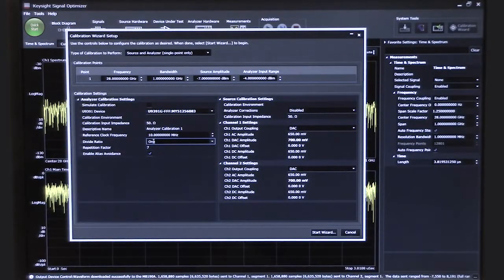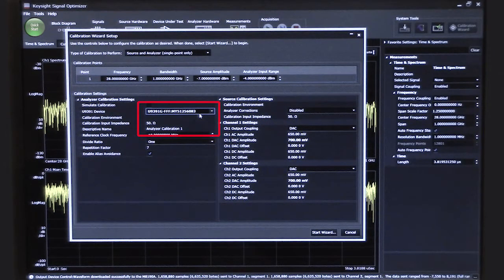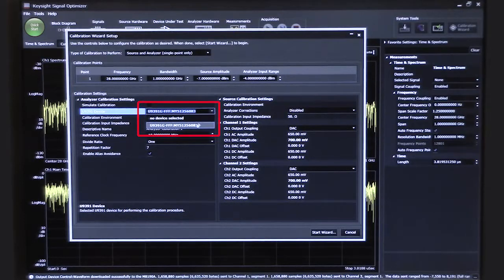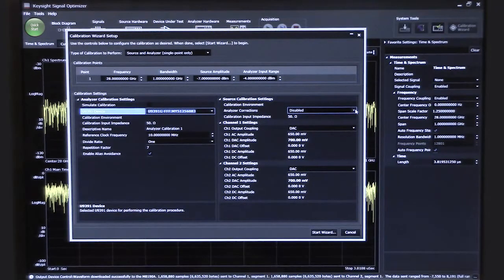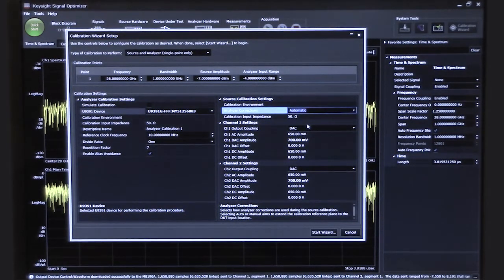On the bottom part of the display, we have more detailed settings for both the analyzer calibration on the left and the source calibration on the right. The most important part on the analyzer side is selecting the comb generator that will be used — this is going to create the test signals we will use to calibrate the analyzer. We can see the model number and serial number of the comb generator. On the right side, we have the source calibration settings, and we want to enable the corrected results on the analyzer side when we do the source calibration. So once we've chosen the settings, we say start the wizard.